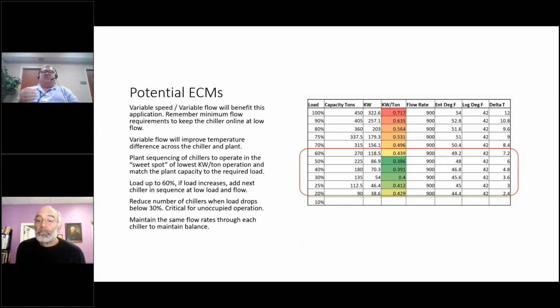I want to get that below 50% of capacity until I have, in this case, 4 machines. If I get all 4 machines running and the load keeps going up, all 4 machines keep going up. That's the best I can do, no matter what, but I'm still running at the lowest kilowatt per ton per machine.